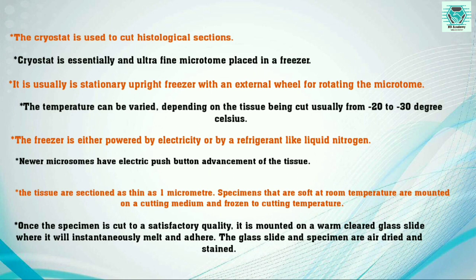Moving to the features of a cryostat: it is used to cut histological sections and is essentially an ultrafine microtome placed in a freezer. It is usually a stationary upright freezer with an external wheel for rotating the microtome. The temperature can be varied depending on the tissue being cut. This freezer is either powered by electricity or by a refrigerant like liquid nitrogen. Newer microtomes have electric push-button advancement of the tissue.